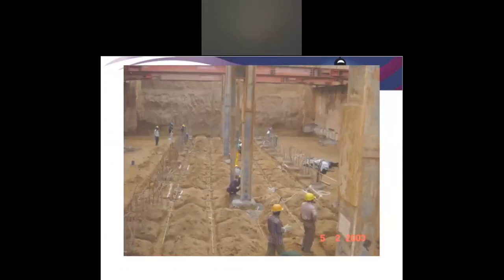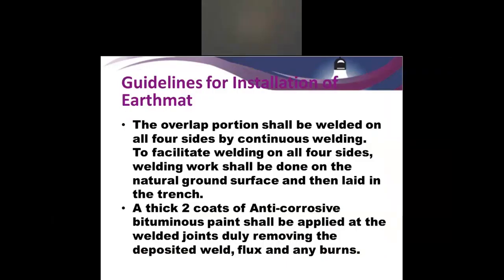Typically, it is like this - you have to run a flat. GI flats are available in maybe 6 meter lengths and are welded together, and whenever you weld, that welding portion should be more than double that area, for overlap.